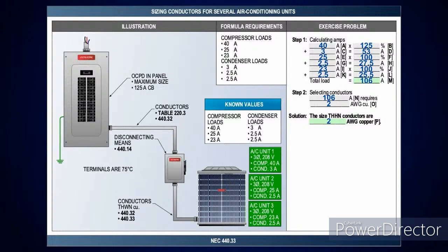Then AC unit number 2 is 25 amps with a condenser of 2.5. Then AC unit 3 is 23 amps with a condenser of 2.5. Well, the largest compressor there is 40 amps, so I'm going to take it at 125%, and then I'll add the 3 amp condenser, which gives me 53 amps.